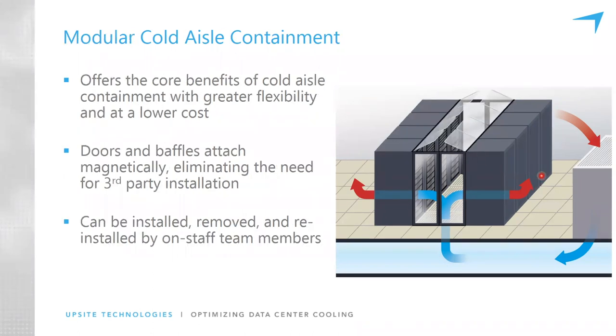When we look at modular or partial cold aisle containment, there's a gap between the baffles and the top of the aisle. This gap does affect the potential for optimizing the balance between supply and demand air. The benefits of modular partial containment are that it can be installed and relocated by staff — it doesn't require third-party installation or construction activities.